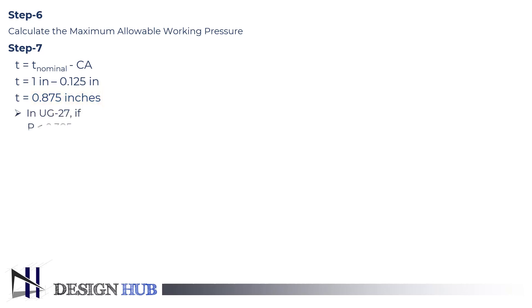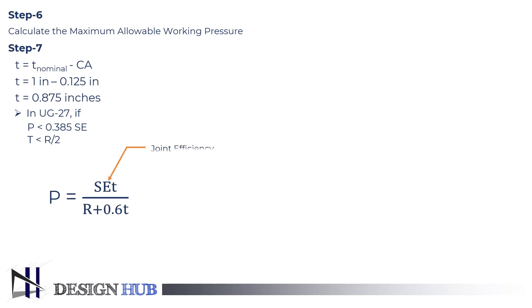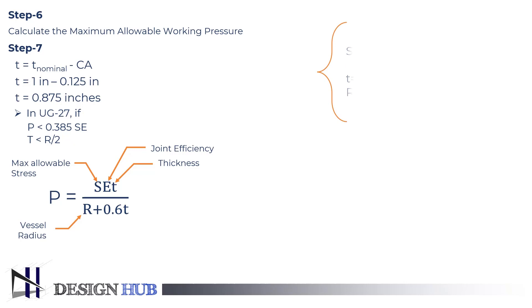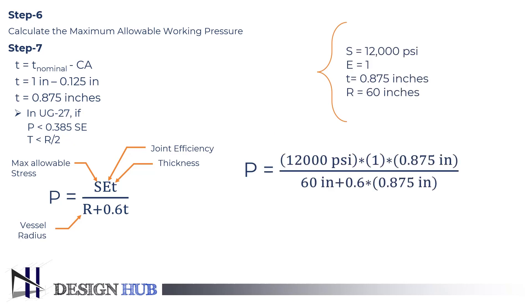According to UG27, if P is less than 0.385 SE, and T is less than R divided by 2, then use the following formula for MAWP. Where E is joint efficiency, T is total thickness, S is maximum allowable stress, and R is vessel radius. Put all the values in the equation and calculate the maximum allowable working pressure. The value we get is 173.5 pounds per square inch.